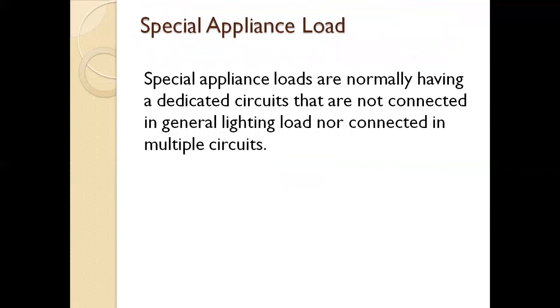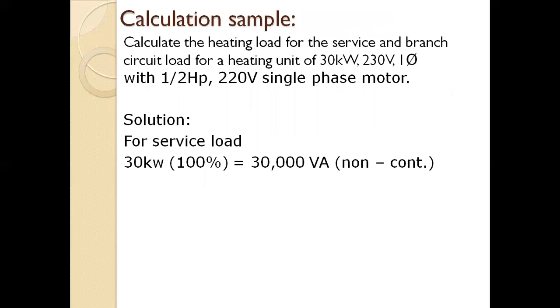Special load appliances. This is what is often overlooked in designs. Special load appliances should be dedicated, so they are not included in a circuit of receptacle outlets. Special appliance loads normally have dedicated circuits that are not connected to the general lighting load or connected in multiple circuits. So we have a calculation sample.